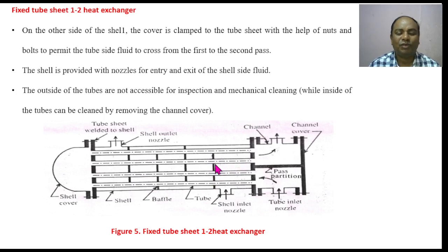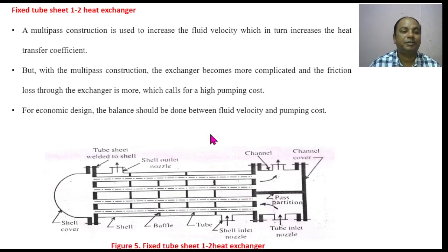So this is a drawback of the fixed tube heat exchanger, as the tube bundles are fixed in the tube sheets, as well as the tube sheet is fixed to the shell. So outside cleaning is not possible, but inside cleaning of the tube bundle is possible.